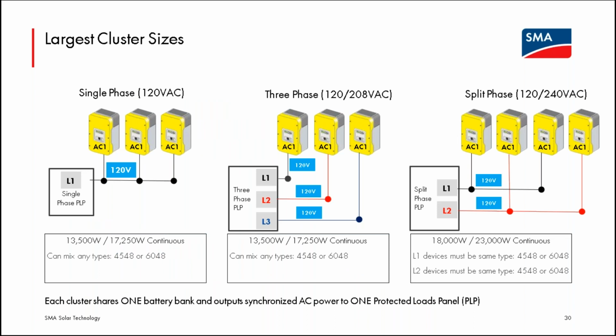A cluster can be a single phase cluster where 1, 2, or 3 Sunny Islands, their AC waveforms are perfectly synchronized, so it's all 120, 60 hertz output. Or they can be told they need to create a three-phase grid, and that would be a 120, 208 three-phase grid. Or it can be a split phase grid where you can have 2 or 4 Sunny Islands, and the output of those will create a 120, 240 split phase grid. So there are lots of options for scaling up. So the maximum size then for a 4 6048 Sunny Island split phase grid would be 23,000 continuous watts just from battery power and the Sunny Islands alone. You can scale up quite a bit of PV to add to that.